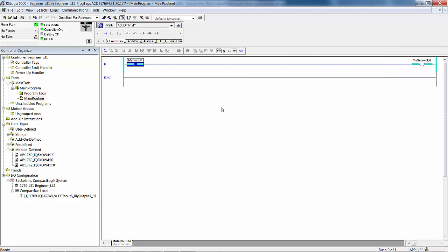When you look at this logic, everything on the left side, logic instructions, are either true or false based on the state of the memory location that they address. They are never on or off. These instructions are never on or off. The bits can be on or off, but the instructions over here, they're always true or false. Output type instructions, actions, are either on or off, never true or false, and they are on or off based on the state of the memory word or bit that they address. They are never true or false. In the manual, we emphasize that.